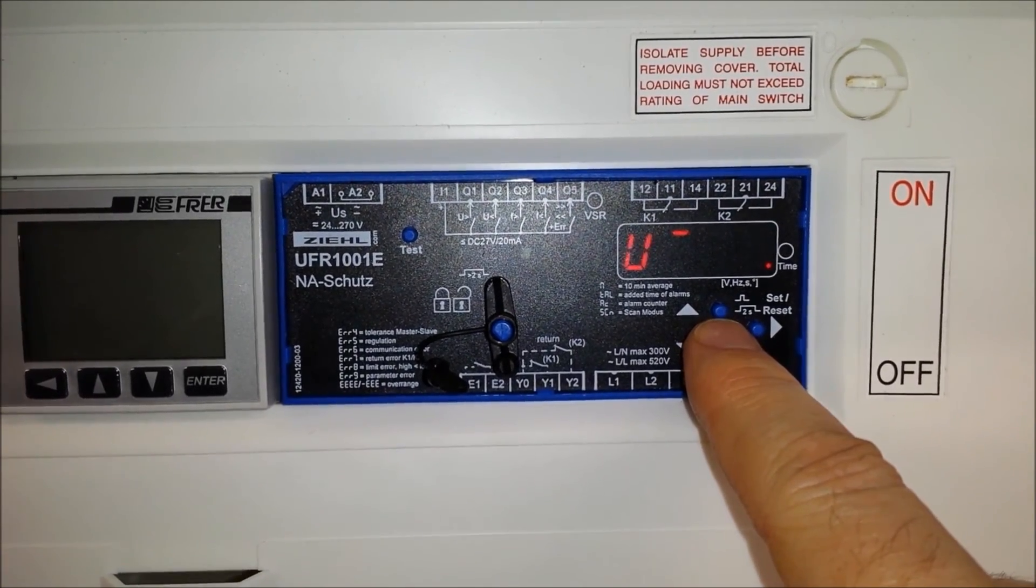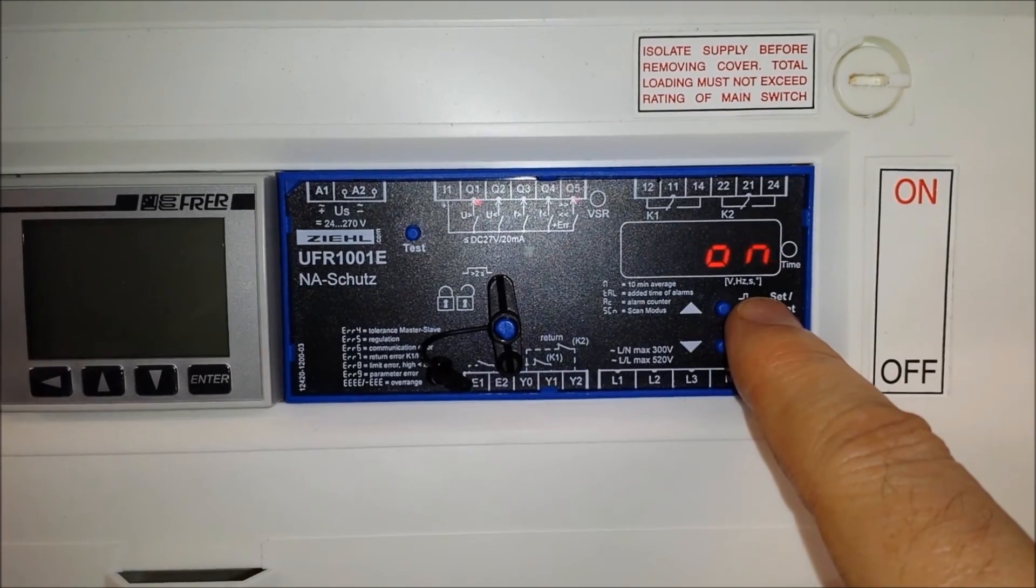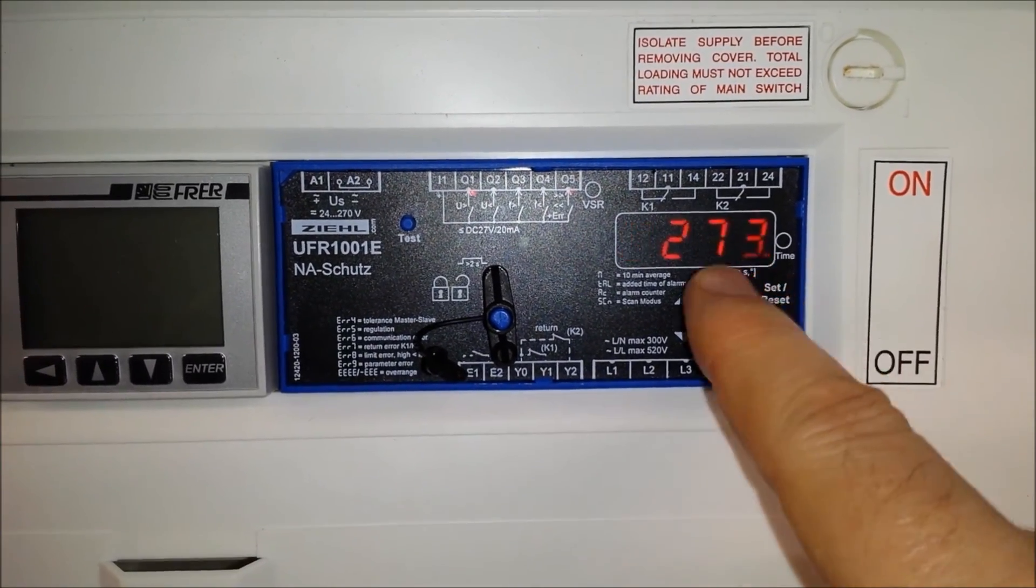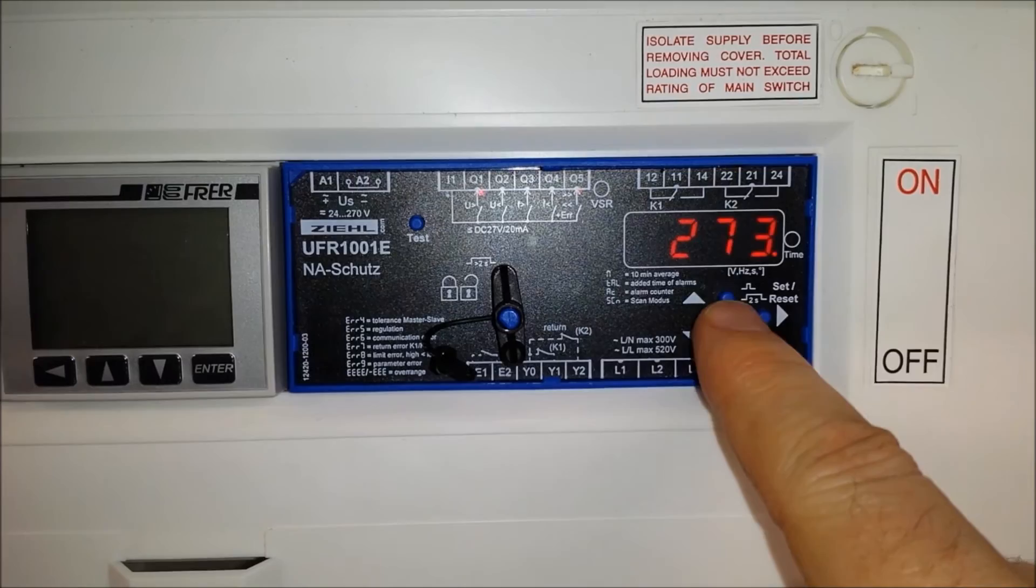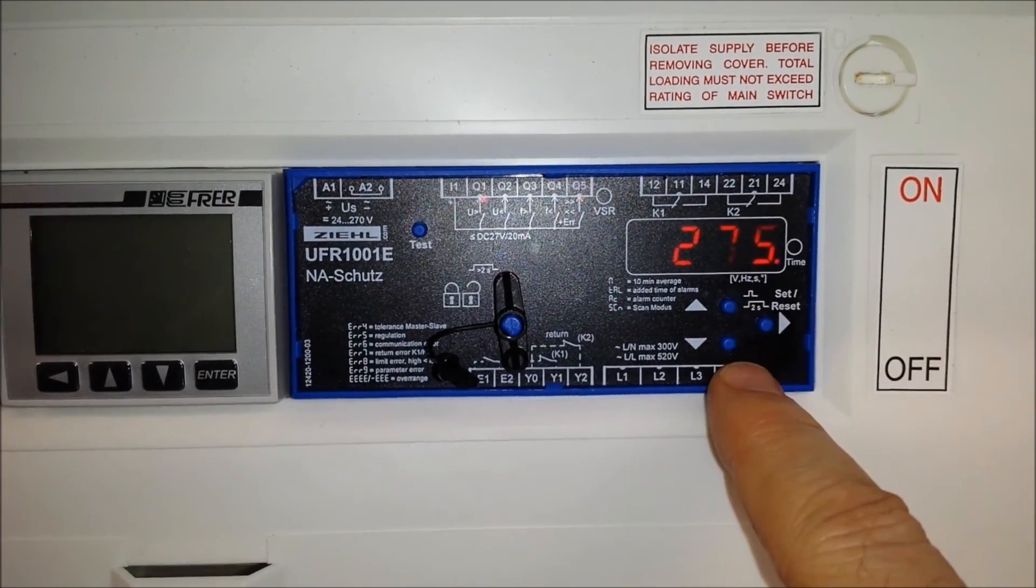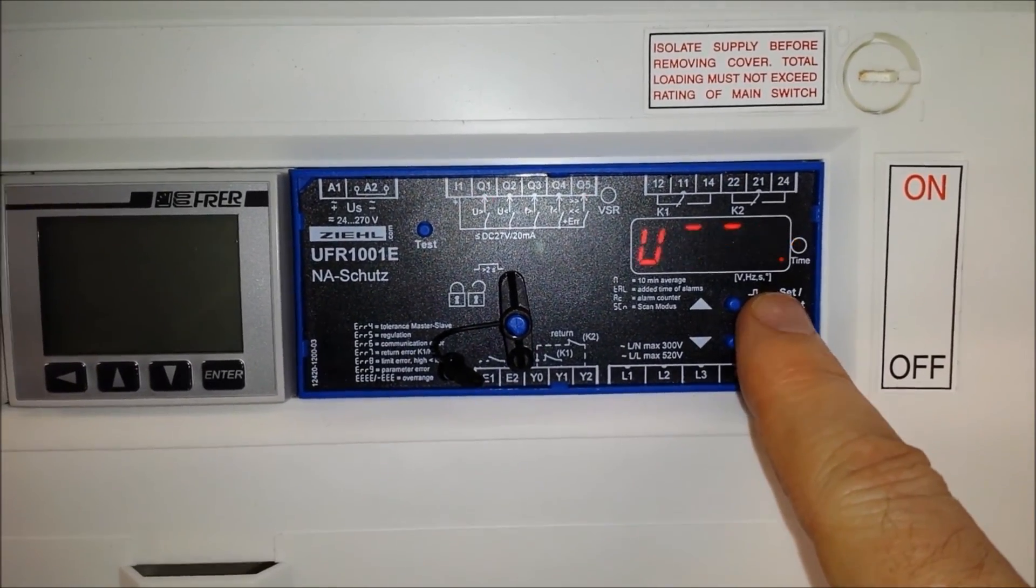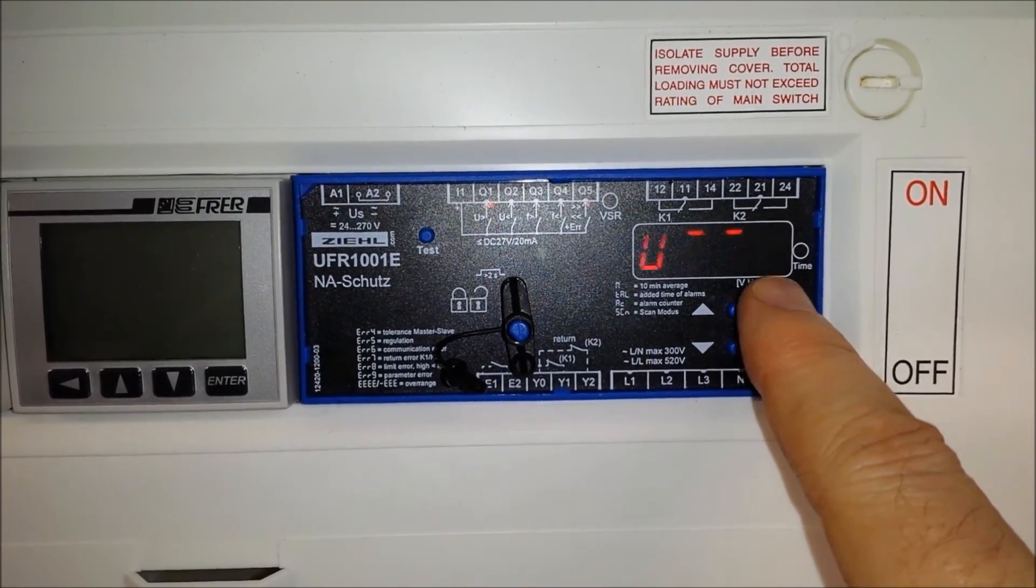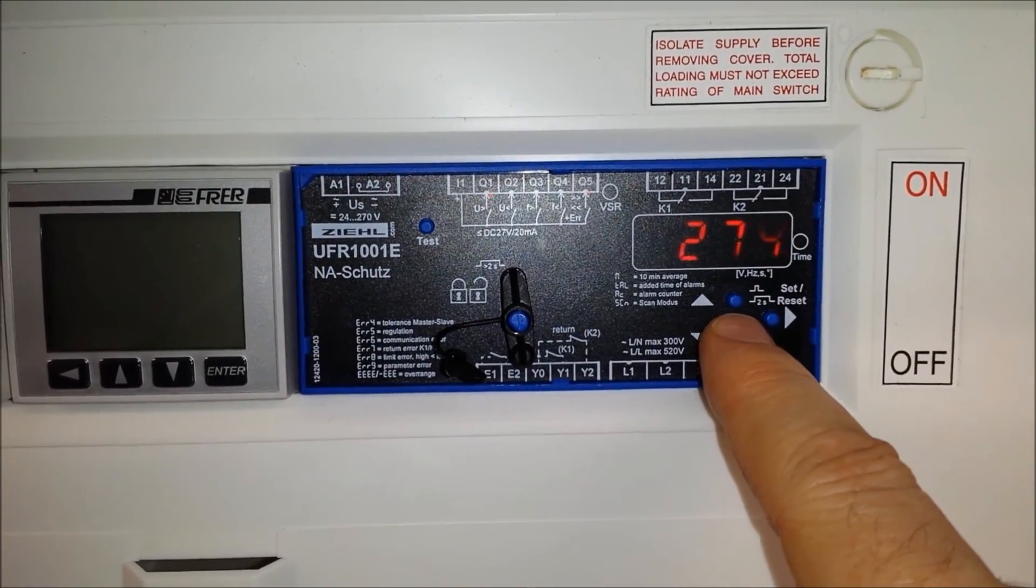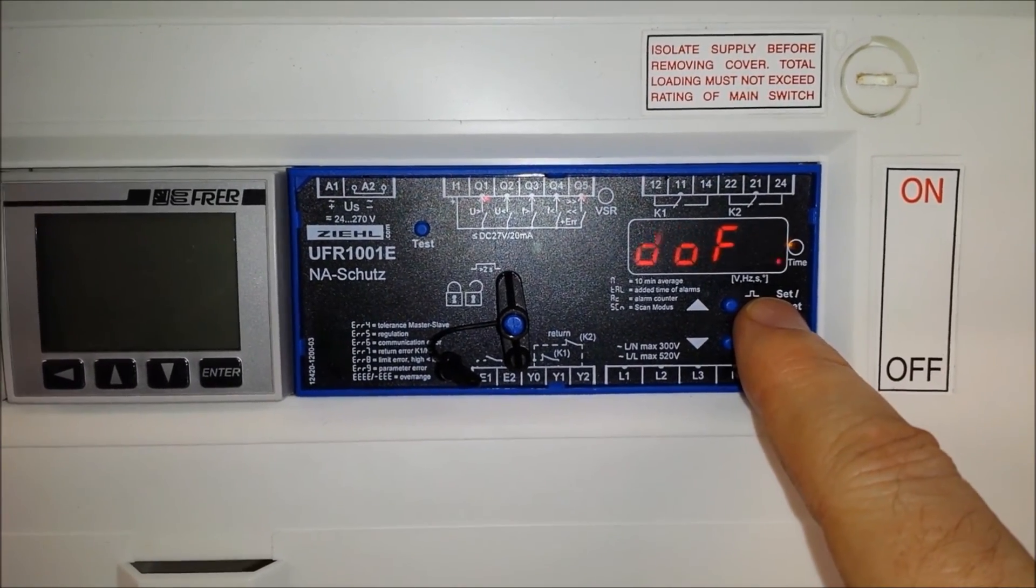Now if you need, because you've got a local transformer which has a slightly different voltage, you need to make modifications. You simply go in, select the value and then using the up down keys you can adjust. So say to 275 and then over you go and you'll find that it's accepted that setting. And then you come over again, check, there's 275. We'll put it back to 273. And the same applies to all the values.